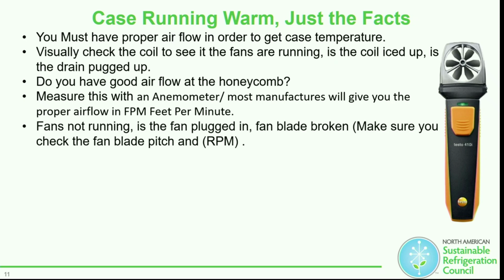Fans are not running. Is the fan plugged in? Fan blade broken. Make sure that you check the fan blade, pitch, and RPM. A lot of these motors are ECM motors. They're little ECM motors, and they'll turn that plastic motor around. I hate to keep saying this word, but Hill Phoenix.